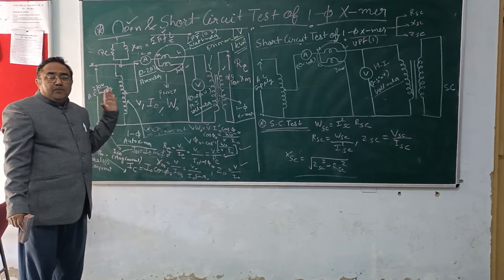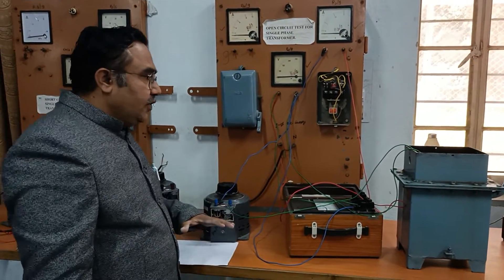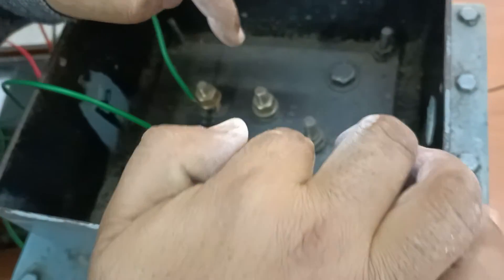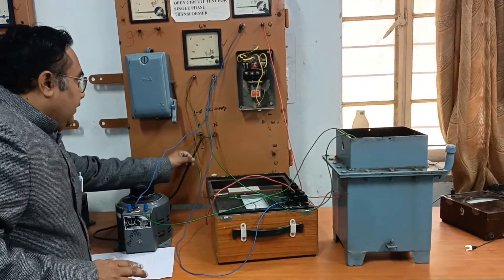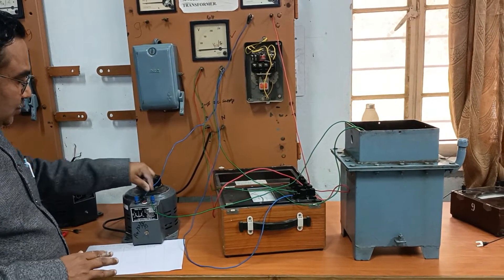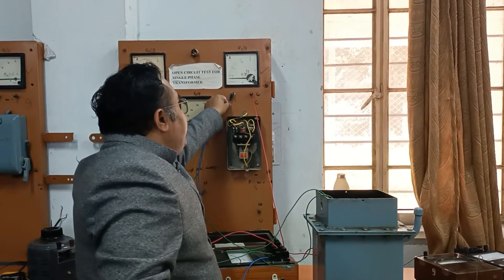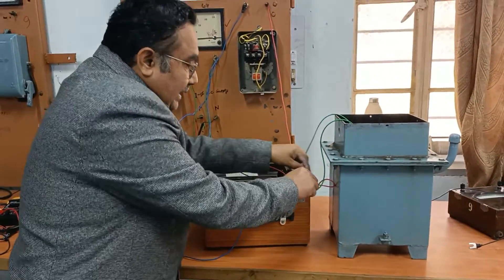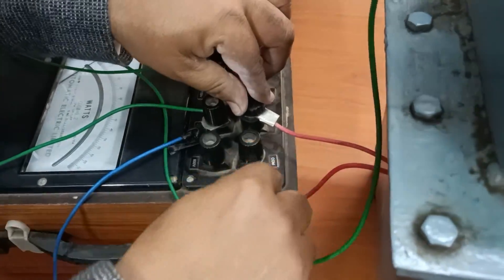Now we will move to the panel of this open circuit test. We are on the panel where we will be conducting the open circuit test for the single-phase transformer. This is our single-phase transformer. You can see these are the two primary terminals - the phase and neutral. The secondary is kept open, so we are not connecting anything to it. We are feeding this transformer with the help of this autotransformer. This autotransformer is being supplied from phase and neutral, and these are its two output terminals.